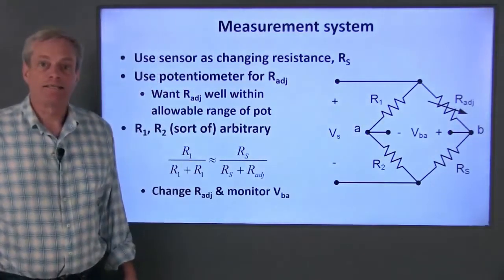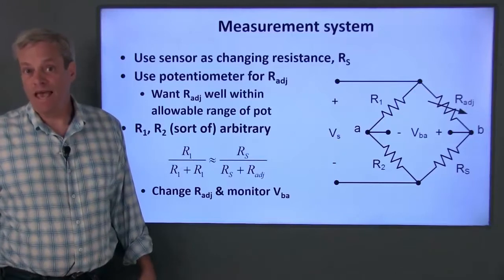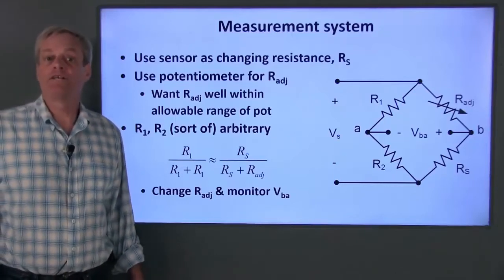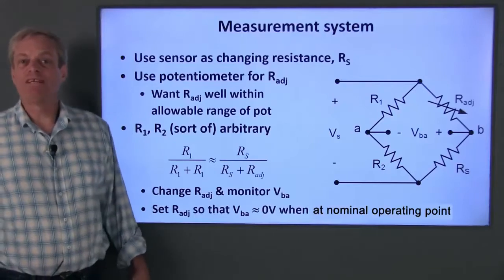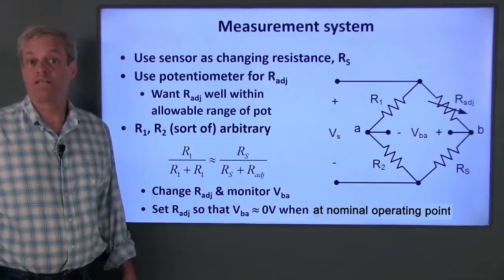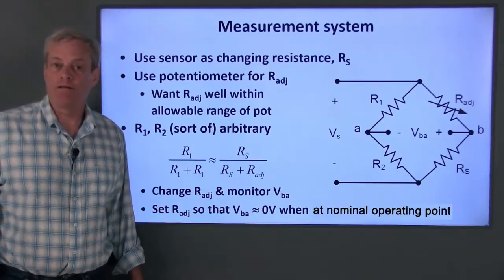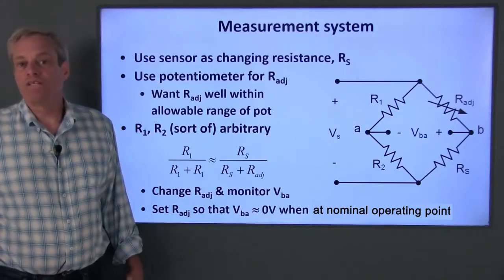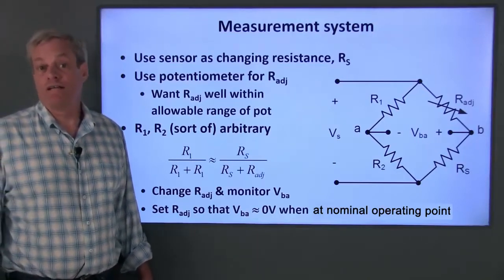To balance the bridge circuit, I can set the value of the pot resistance by monitoring the voltage V sub Ba with a voltmeter while I adjust the potentiometer's resistance. If I use this approach, I don't really care what value the pot resistance actually is. I just change the potentiometer position until the measured voltage is zero when the sensor is at its nominal operating point. I just need to make a reasonable first guess for the resistances and then the potentiometer can do the fine tuning for me.